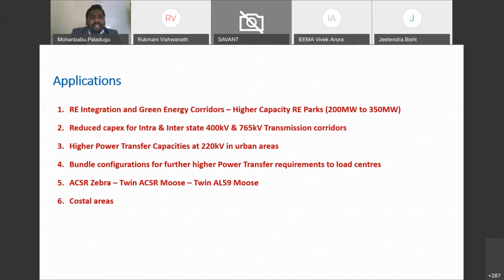Then for planning at 400 and 765 kV lines, we plan Moose and Hexa Zebra lines at 400 and 765 kV. Again, as I said, because the tower weight can be reduced and conductor weight is reduced, you will have reduced capex for those intra and interstate lines at 400 and 765 kV.